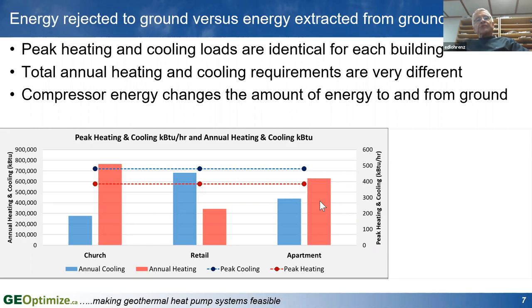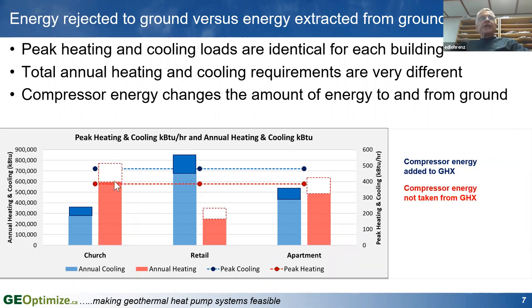heat pumps operate with electricity. The heat that's generated by the electricity has to go somewhere. When you're cooling, that electrical energy ends up being shoved into the ground. So that increases the amount of heat that's being rejected to the ground. And when you're heating, some of the compressor energy, the electricity used to run the compressors, ends up going into the building. So what that does is take away some of the heating load, and that changes the balance a bit more. So you can see that in this building, the amount of heat rejected into the ground is very, very similar to the amount of heat that's taken from it. So this would be considered a balanced system, balanced energy loads.